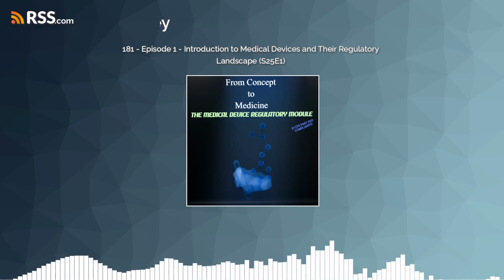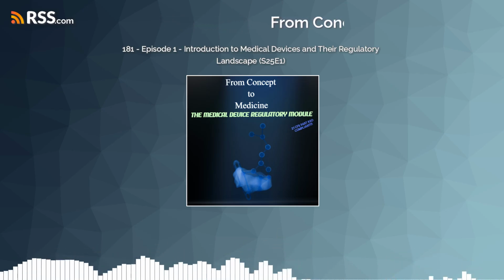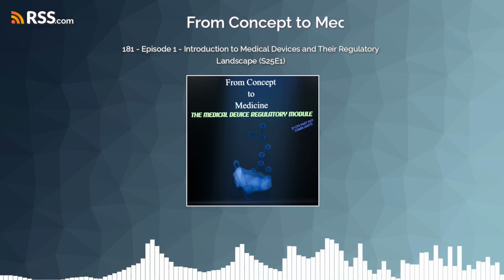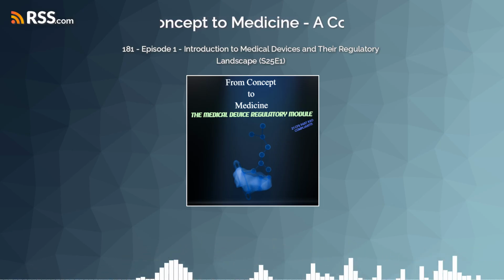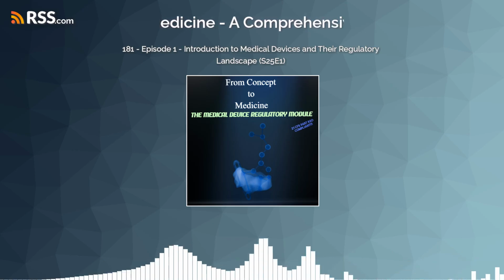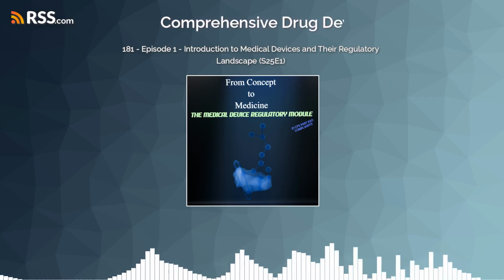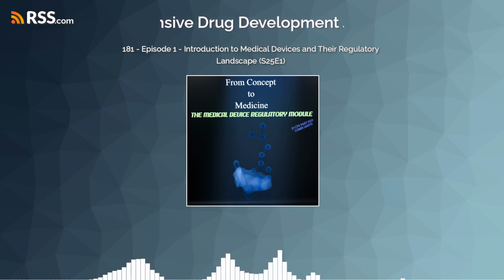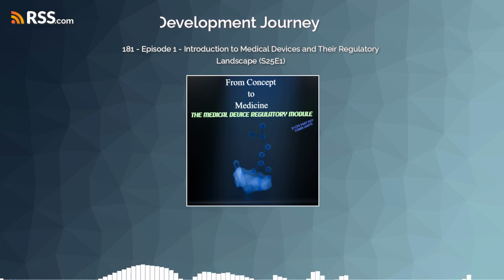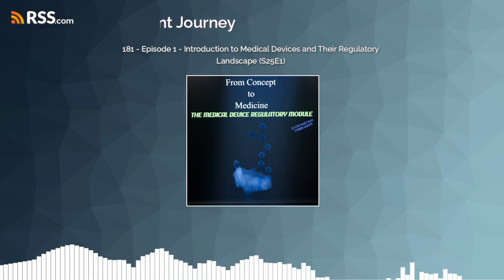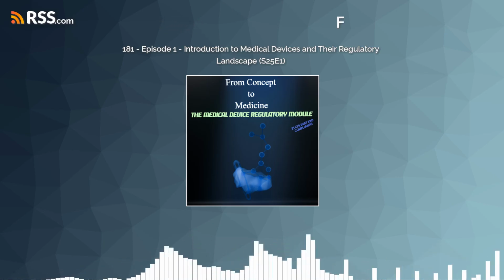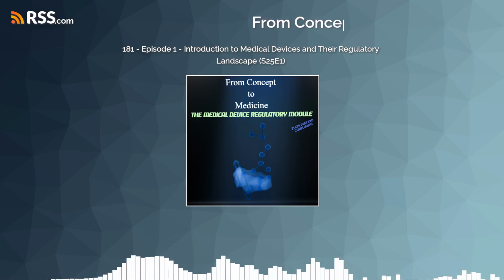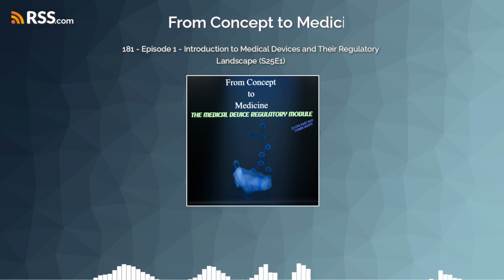So it's third-party auditors doing the review, not the government agency directly like the FDA. For most devices, yes. This contrasts sharply with the FDA's model, where FDA's own scientists and reviewers conduct that centralized scientific review of the pre-market submission, like the 510(k) or PMA. That's a huge difference in approach. It really is. In Europe, getting that CE mark indicates compliance and allows marketing across the EU member states.